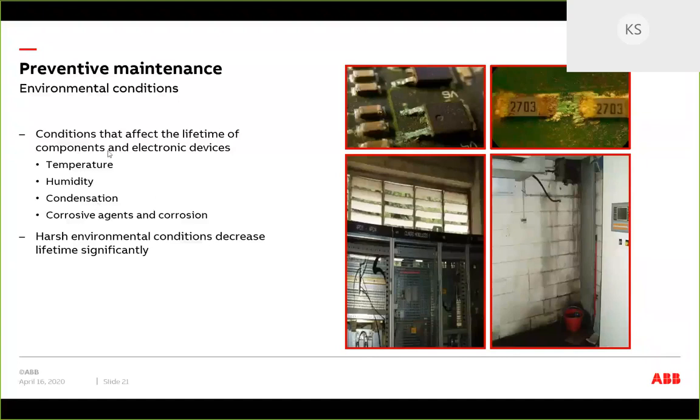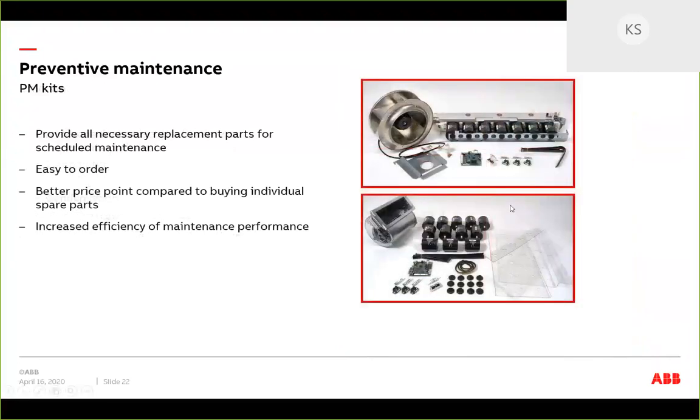This next picture here is, let me get back there. There we go. Your preventive maintenance kits. You want to explain? This is your fan you were talking about, isn't it? Yeah, that's one of the fans. There's a couple of different versions of the fans and what would be included in a kit. The can style capacitors are there. Looks like a power supply board and probably some discharge resistors. Those are some of the really common parts in those kits.